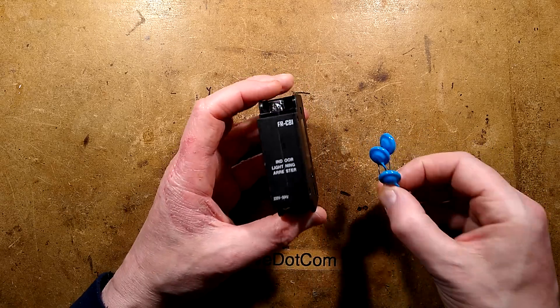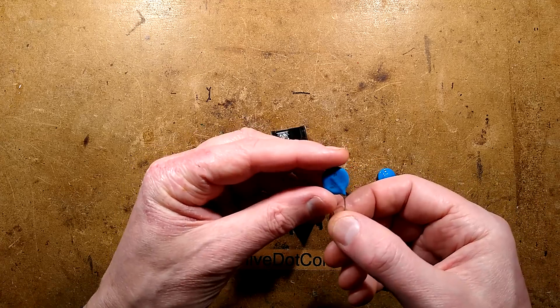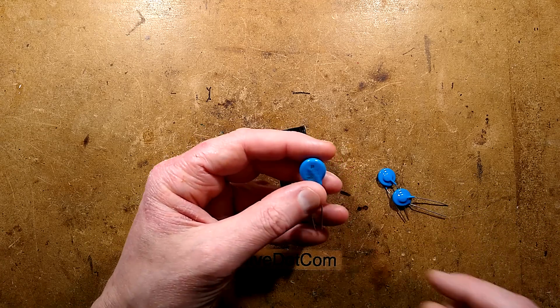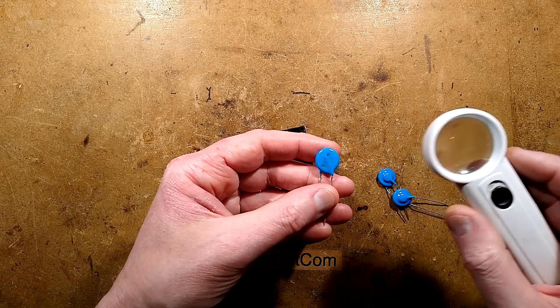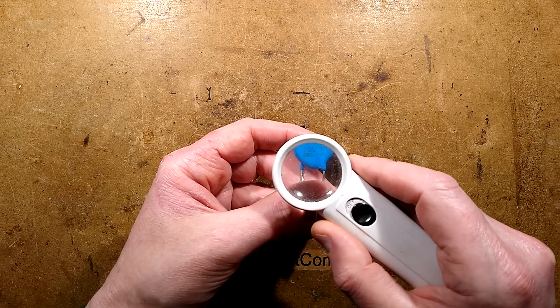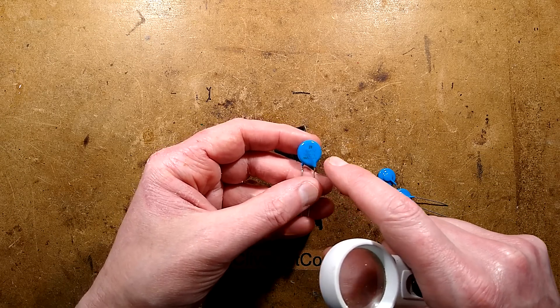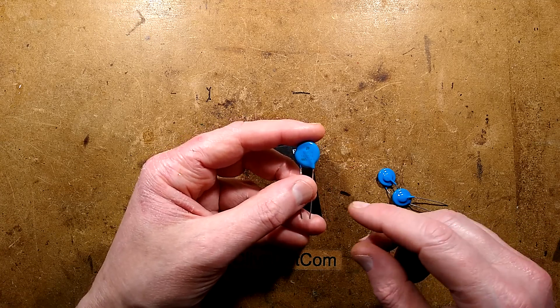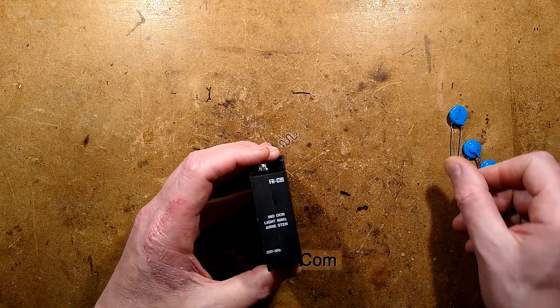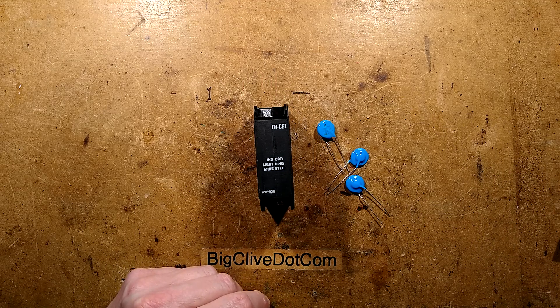Frank suggested that I test these with high voltage — what a great idea — and then I'll open it up and see what's inside. He also sent these combined metal oxide varistor and gas discharge tube (GDT) components. The GDT is a gapped gas-type device for transients. This one is rated 14D251K: 14mm diameter disc, and 251K means it starts turning on at 250 volts. That's quite low — maybe for 120 volt systems.